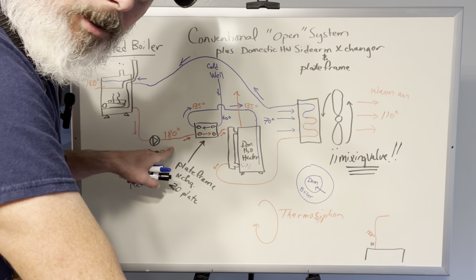This is very, very important. The water coming out of this water heater, depending on how big your plate frame heat exchanger is, depending on your boiler water temperature, will be very hot, dangerously hot, scalding hot. So before that gets sent to the house, I'm going to draw it over here. This would be the hot coming out of the water heater. I'm only going to draw the hot, but this water could be, good gracious, 150 degrees, 180 degrees. Over time your sidearm is going to heat this up to whatever your boiler water is. So this could be devastatingly hot.